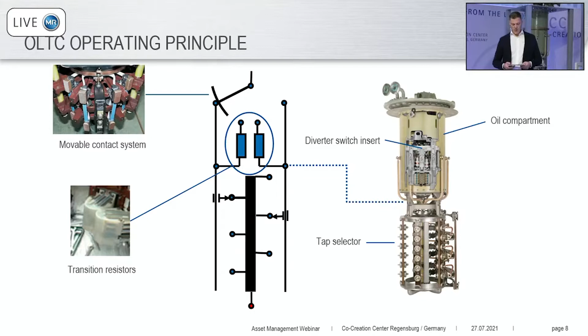Now let us have a deeper look into the different OLTC technologies. On the left side, you see the conventional, already known technology, and on the right, our VacuTap technology. The main difference is in which medium the switching process takes place. On the left, we're switching in mineral insulating oil, and on the right side, we're switching inside the vacuum bottle. So you can see that we no longer have any carbon particles as we are switching in our vacuum bottle. It's more or less a completely sealed system. So we're using the insulating oil just for insulating purposes, for cooling and lubrication. On the left, we are also using the oil for arc quenching, and therefore we have carbon particles inside our insulating oil.